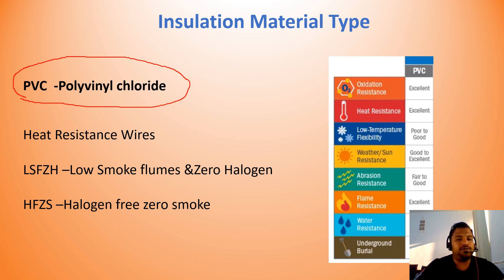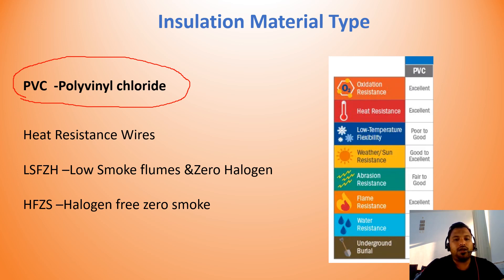LSF-ZH cables are used in high-density population areas, because during a fire, PVC wires can produce halogen and smoke, which causes suffocation and increases the chances of human death. That's why LSF-ZH and halogen-free smoke cables are used in high-density populations. For a single, double, or triple storey domestic building, these are not recommended as they increase cost. Fire rated cables are also available, used in high-risk fire areas such as fire alarm systems and emergency light systems, but are not required for domestic G+1 or G+2 buildings. For those, general PVC wires are sufficient.